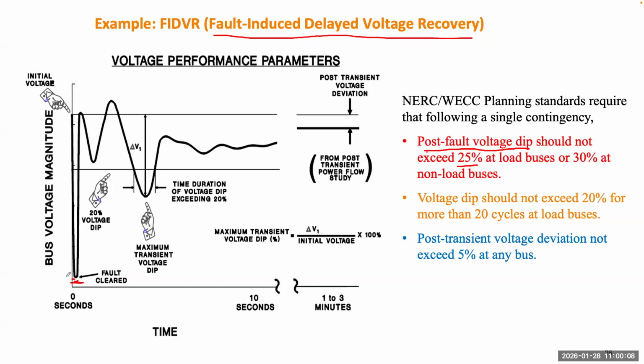If it's lower than this, the power company needs to figure out what they can do, maybe add a capacitor to support the voltage or some other controller. That's for a load bus. If the bus has no load, it's just a substation connecting other transmission lines, so the voltage can be 0.7 per unit.